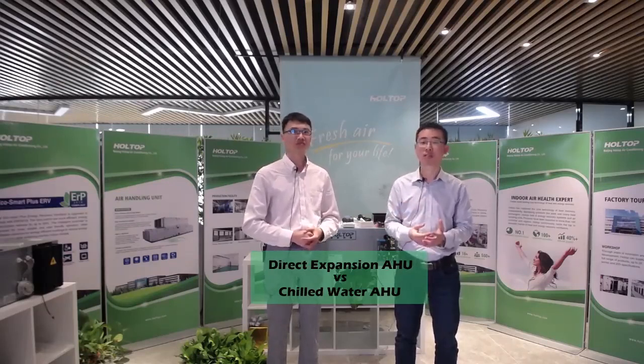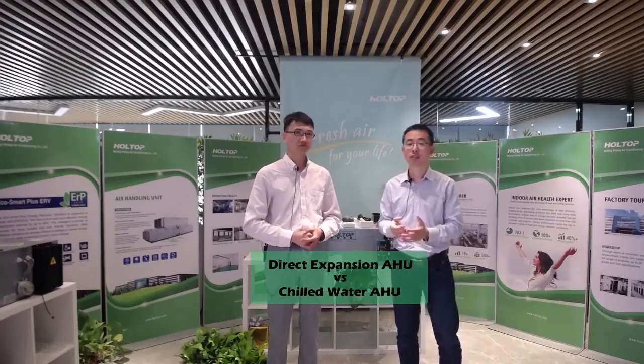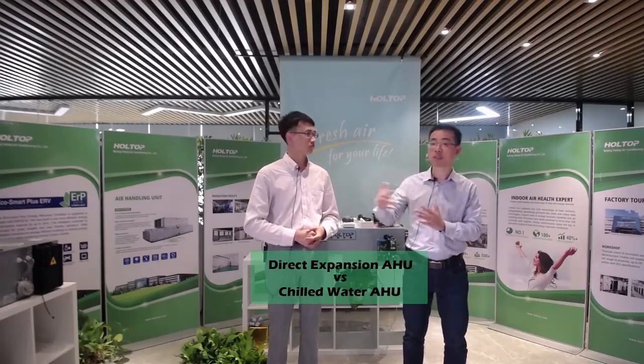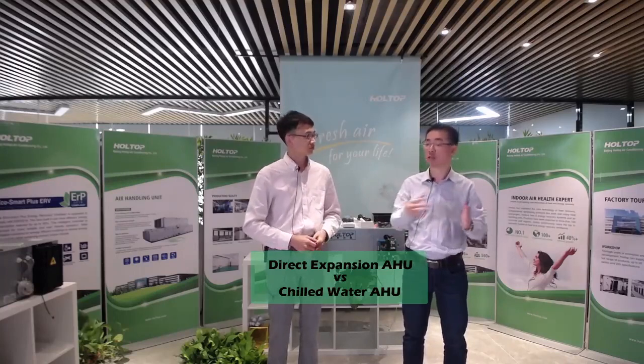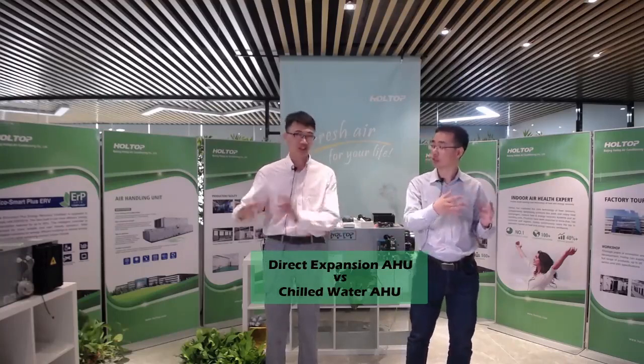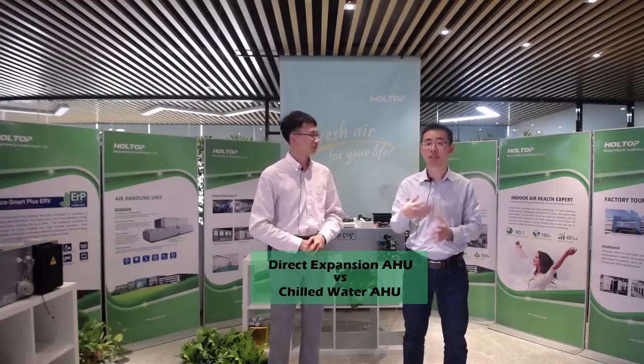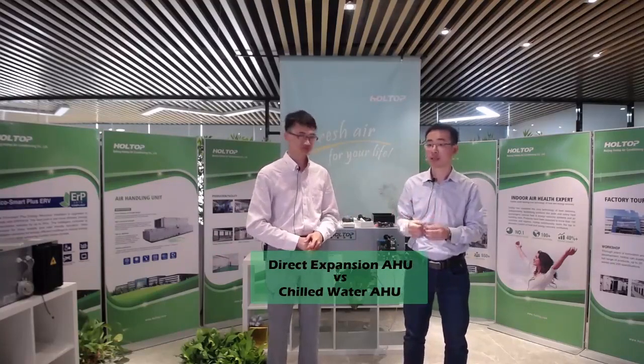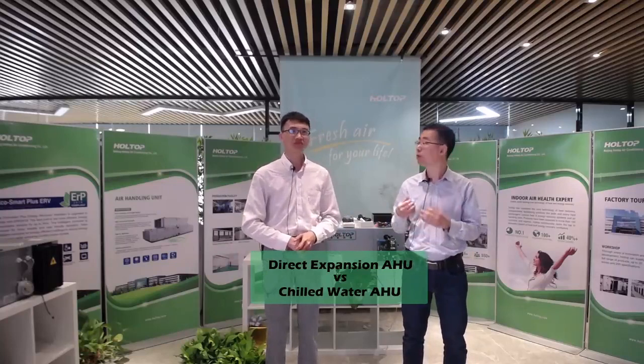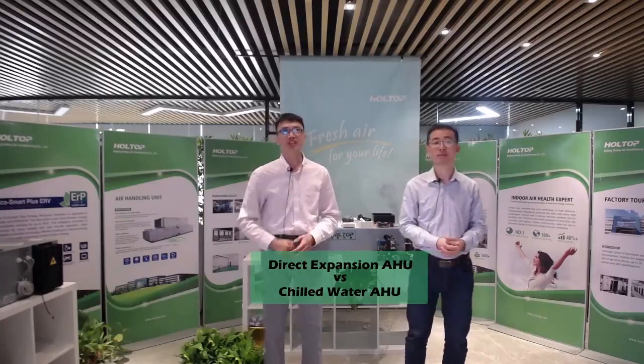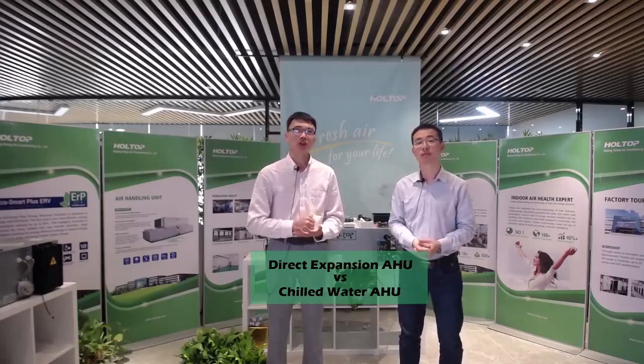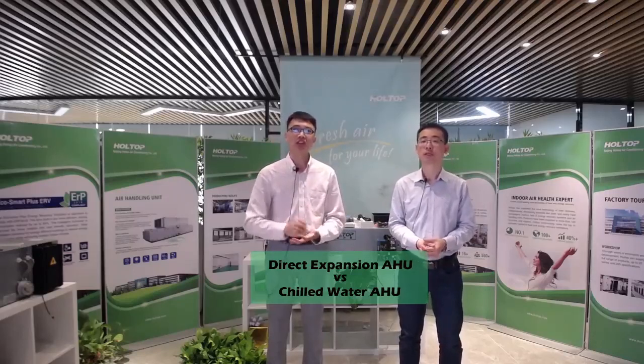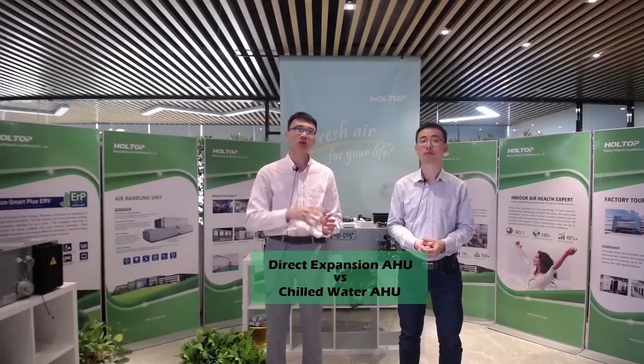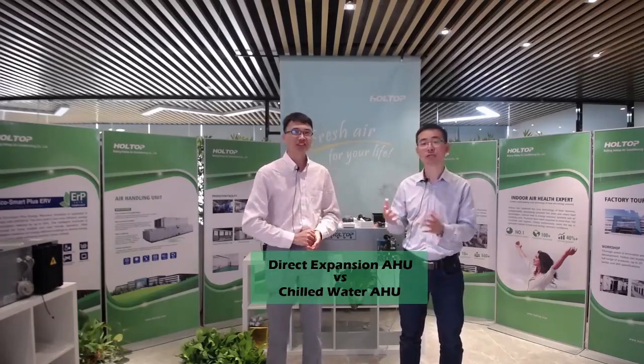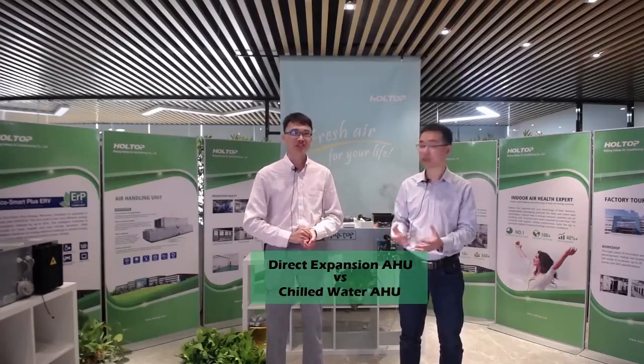And in the DX system of central air conditioner, the refrigerant travels only a small distance between the outdoor unit and indoor unit. So the additional heat absorption is less, which makes the DX system more efficient. So in short, DX AHU is more efficient than chilled water AHU on heat exchange to evaporate and refrigerant delivery, right? Yes. Besides, there are also some key advantages of a DX coil system.